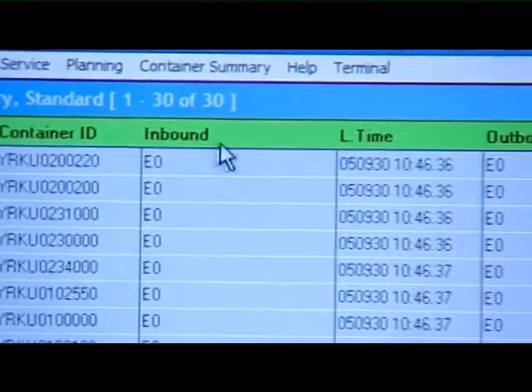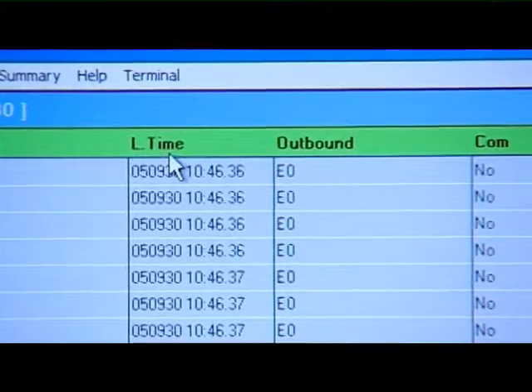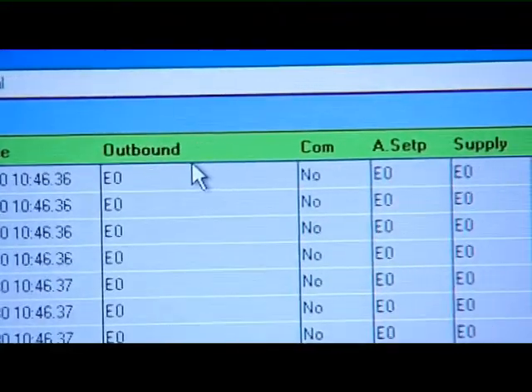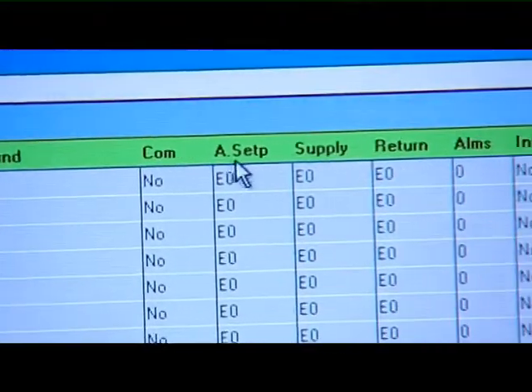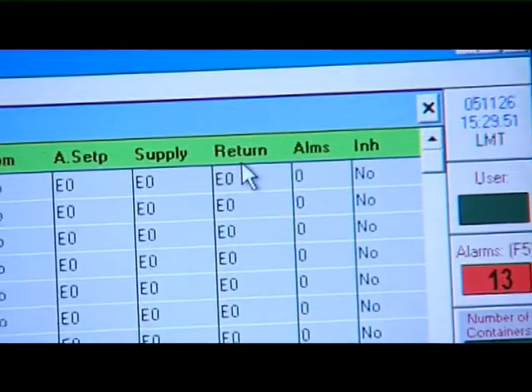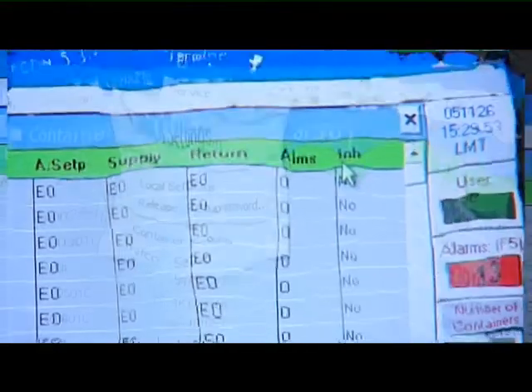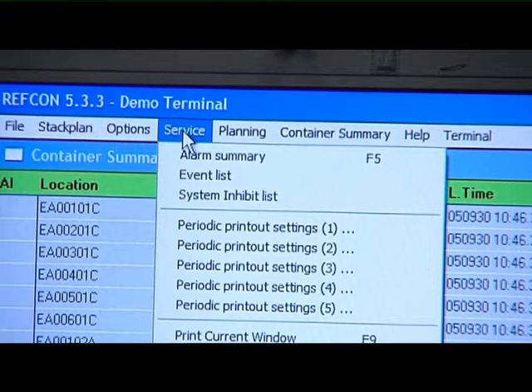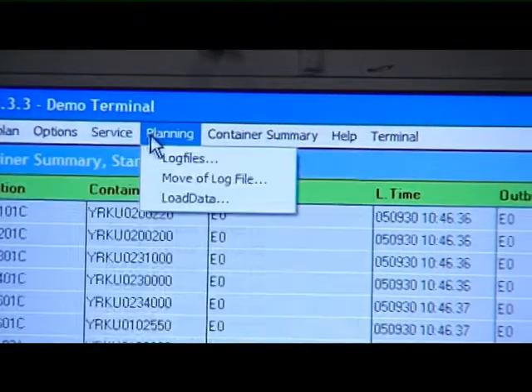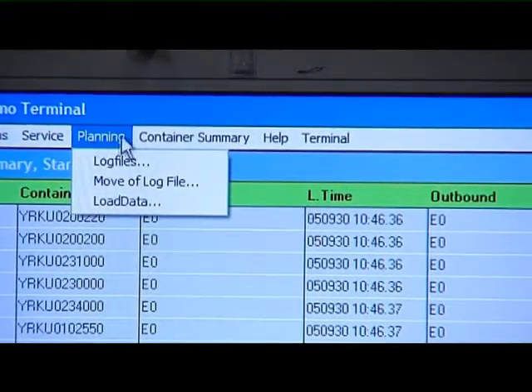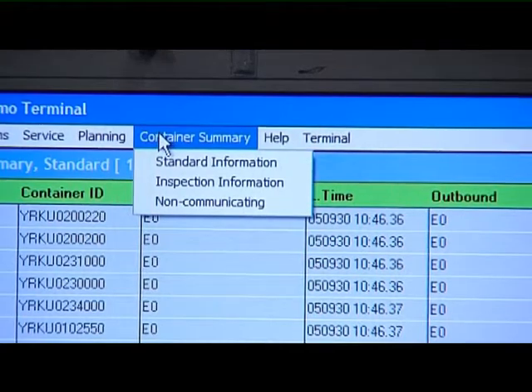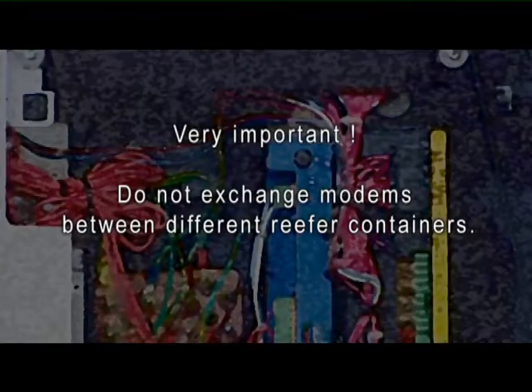Through this PC, the vessel monitoring system can constantly monitor the reefer containers and will also, in case of a malfunction, indicate an alarm. Amongst the options available on the PC station are the change of the set point and the change of the container ID. Very important, do not exchange modems between different reefer containers.